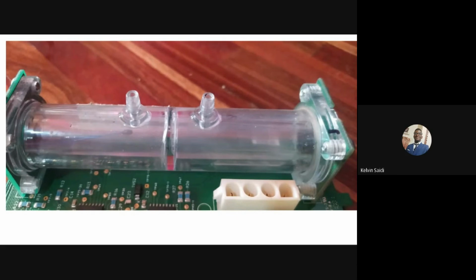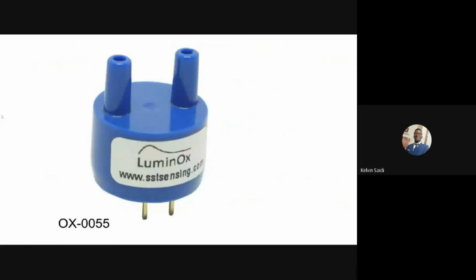Now let's go to the optical sensor. And the concept behind an optical sensor is the oxygen-induced quenching of fluorescence. So they rely on a photosensitive material that will respond to light. They have a light source and a light detector. So oxygen has a tendency to absorb light. So when exposed to light, some substances will emit light energy. And if this process happens in the presence of oxygen, as I've already mentioned, that oxygen will absorb some of the light that is produced.